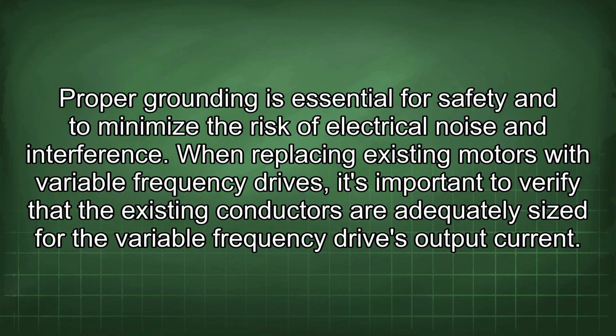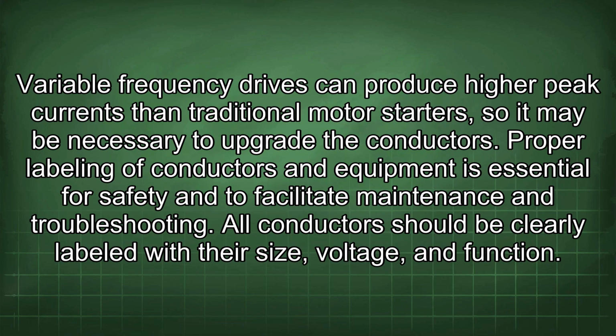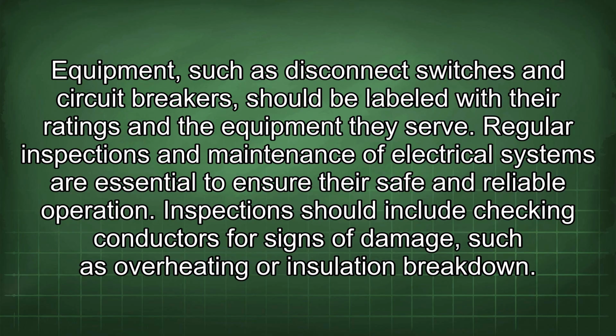When replacing existing motors with variable frequency drives, it's important to verify that the existing conductors are adequately sized for the variable frequency drive's output current. Variable frequency drives can produce higher peak currents than traditional motor starters, so it may be necessary to upgrade the conductors. Proper labeling of conductors and equipment is essential for safety and to facilitate maintenance and troubleshooting. All conductors should be clearly labeled with their size, voltage, and function. Equipment, such as disconnect switches and circuit breakers, should be labeled with their ratings and the equipment they serve.